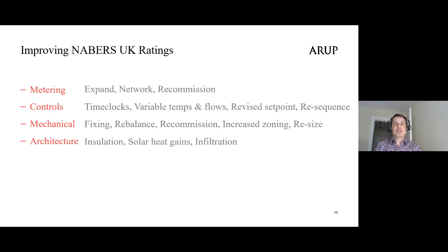Controls are another area Danny touched on, but there's usually a lot that can be done, even just checking time clocks. Many buildings in the UK have controls that assume 100% design occupancy from 9am to 6pm, but BCO research shows that never actually happens. Average occupation is around 60-70%, let alone first thing in the morning, last thing in the day, or over lunchtime. Updating controls to be demand-led, responding to the actual demands of the building, can result in the equivalent of a 1.5 star improvement in a NABERS rating.